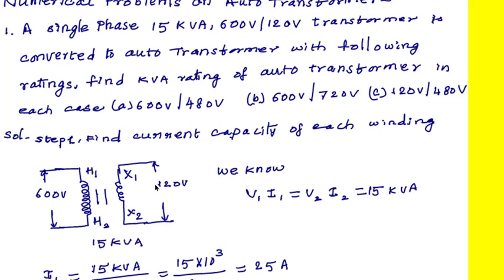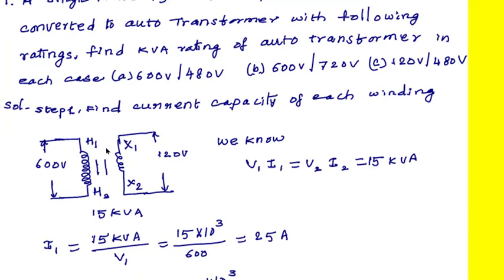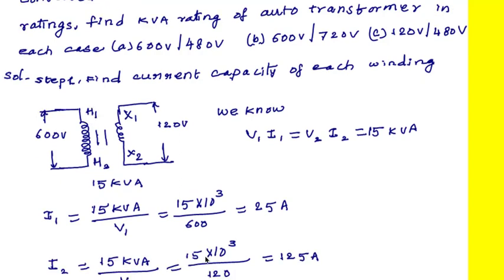Next, the 120-volt winding current capacity. The current that flows is I2, and the terminal voltage is V2. So V2·I2 = 15 kVA, giving I2 = 15 kVA ÷ V2 = 15×10³ ÷ 120 = 125 amperes. This is the low-voltage winding current-carrying capacity. The high-voltage winding current capacity is less, whereas the low-voltage winding capacity is more.